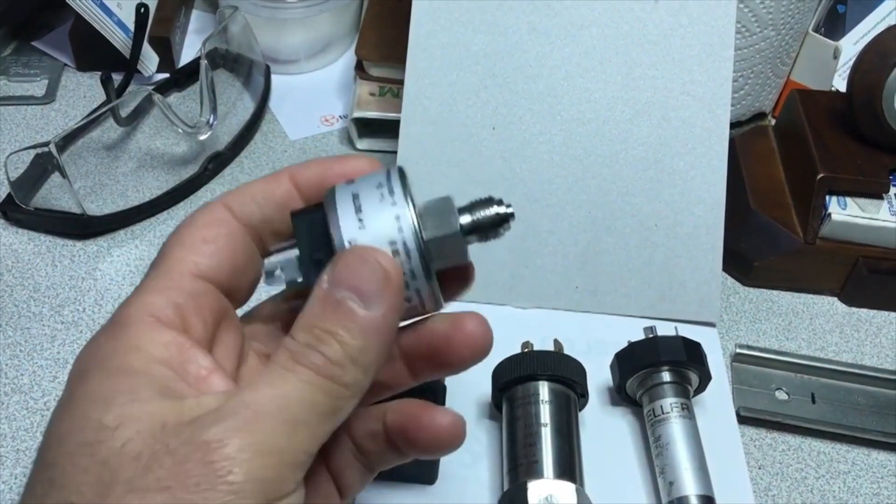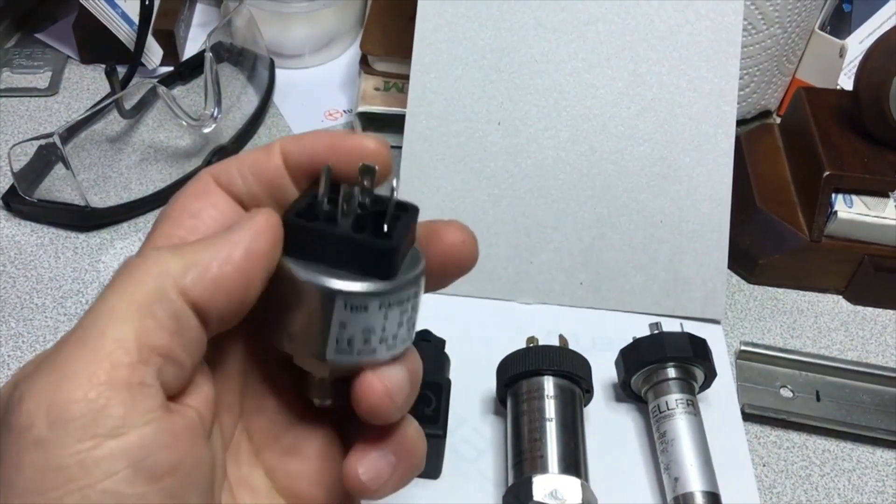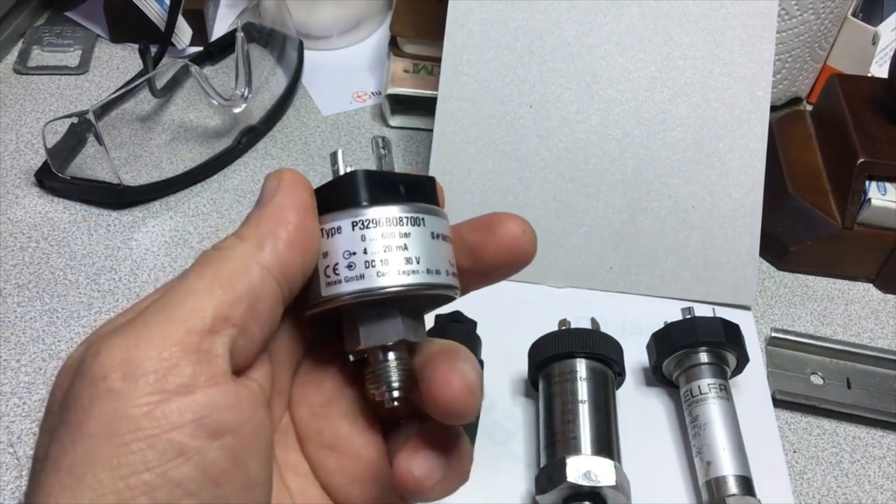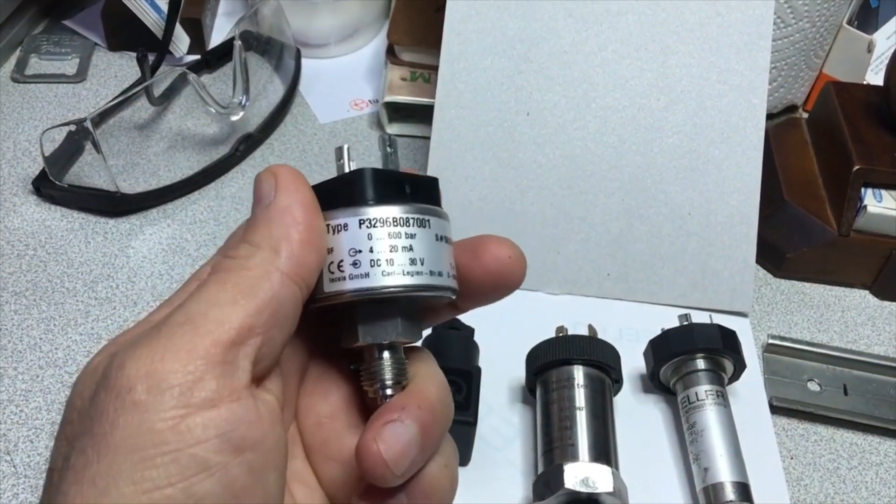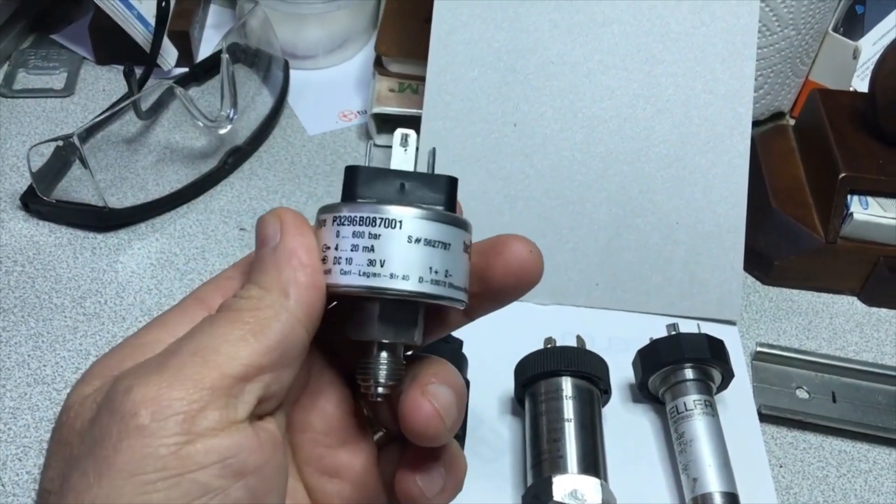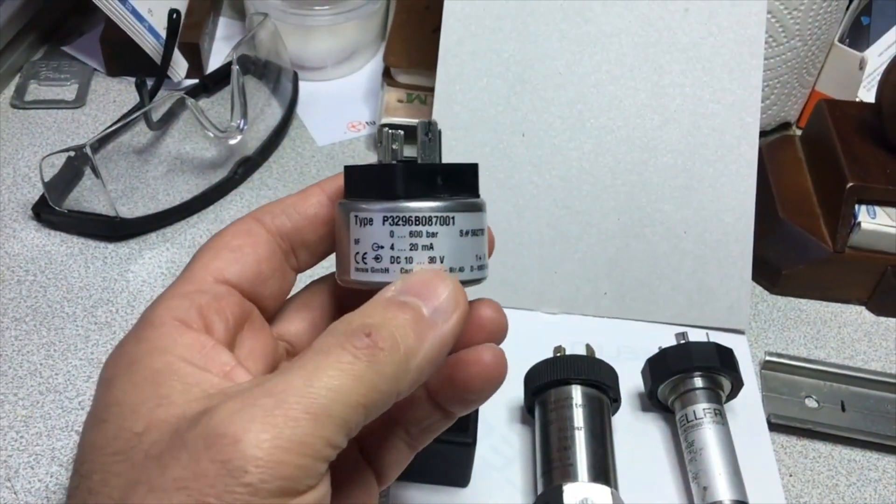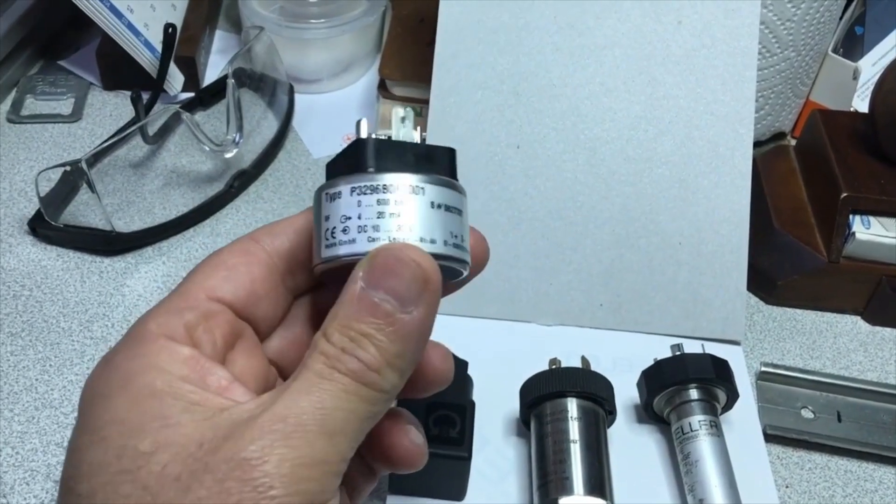However, 4 to 20 milliampere sensors are the most reliable and most accurate. Let me try to explain it this way. Types that give 0 to 10 volts output make accurate measurements at close points, but when we want to carry them to long distances, we may read incorrect values because voltage drops will occur on the cable.